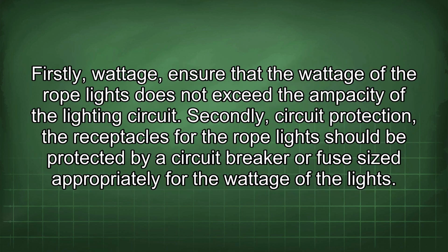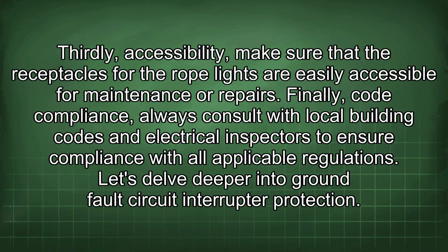Firstly, wattage. Ensure that the wattage of the rope lights does not exceed the ampacity of the lighting circuit. Secondly, circuit protection. The receptacles for the rope lights should be protected by a circuit breaker or fuse sized appropriately for the wattage of the lights. Thirdly, accessibility. Make sure that the receptacles for the rope lights are easily accessible for maintenance or repairs. Finally, code compliance. Always consult with local building codes and electrical inspectors to ensure compliance with all applicable regulations.